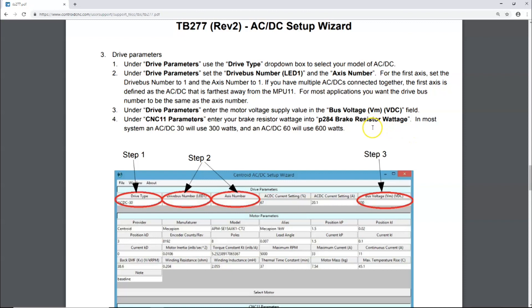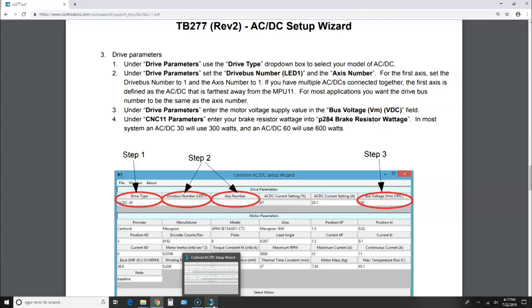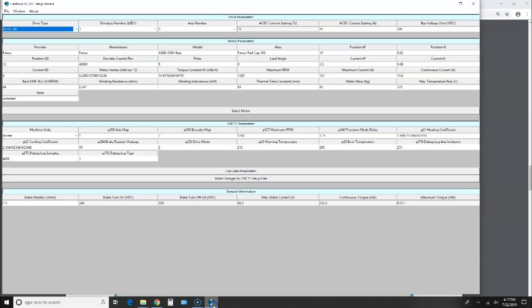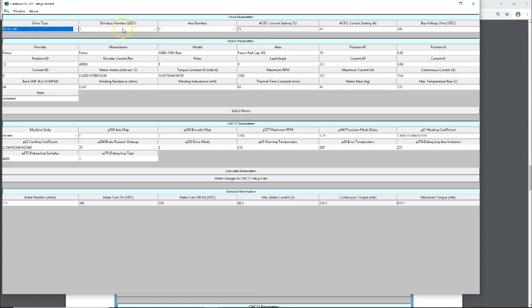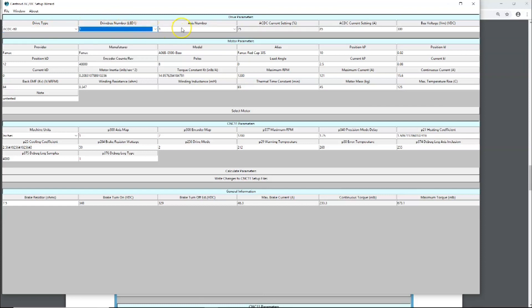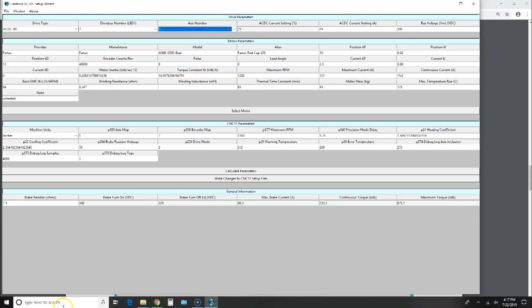Let's check drive parameters, drive type, drive number, and access number. There's our AC/DC. They have 30s and 60s, I have a 60. Drive bus number is one. You can see there's up to eight, but we are working with one. It is axis one, so that's correct. Then these current settings and bus voltage. Here's the bus voltage. This drive happens to use rectified 240 volts AC, so the bus voltage is 300 volts DC. We've got that part done, and we've got the bus voltage correct.